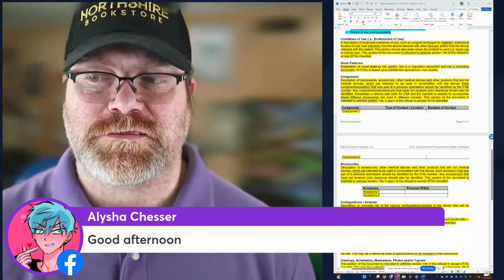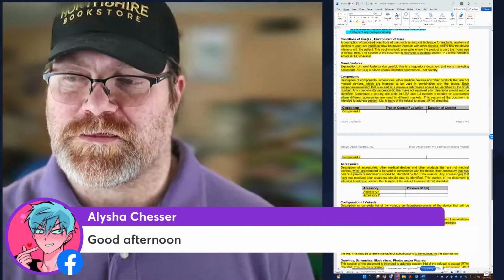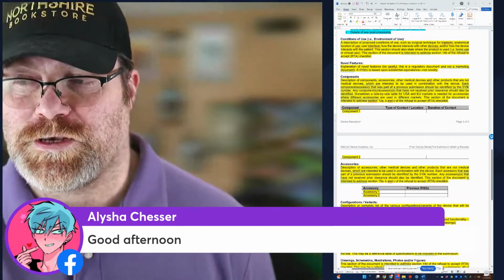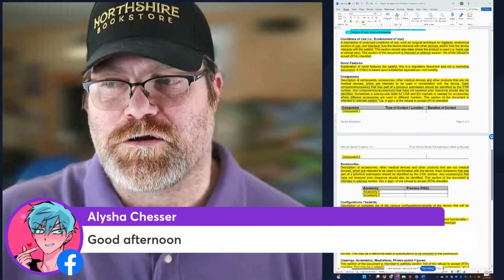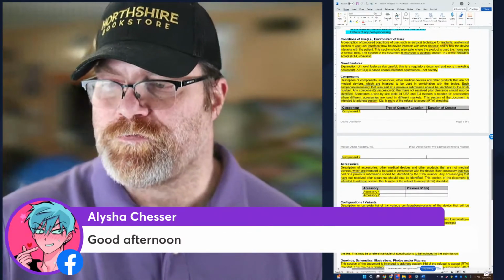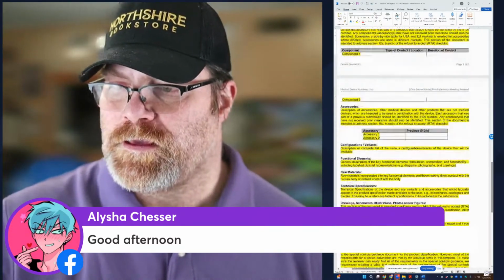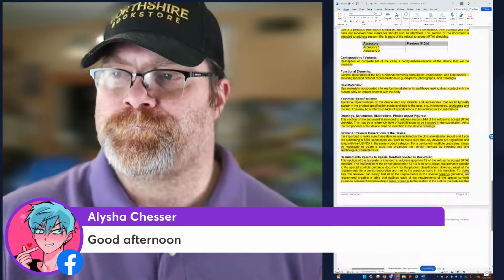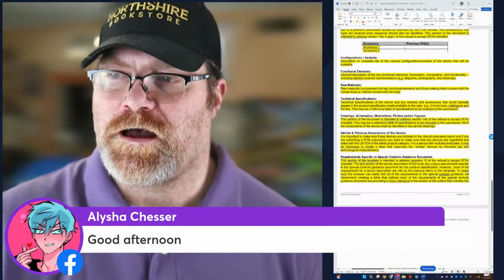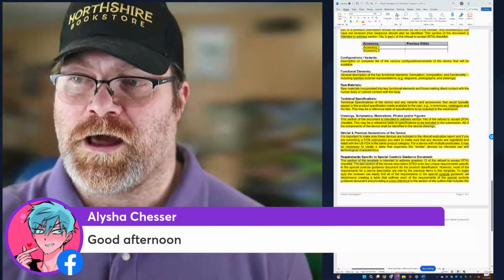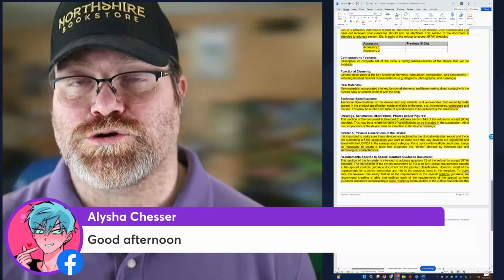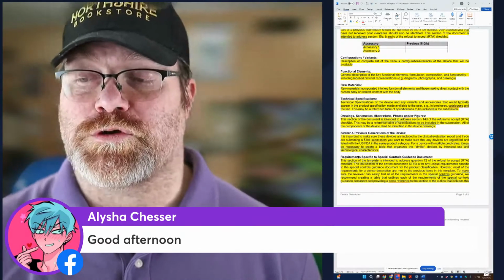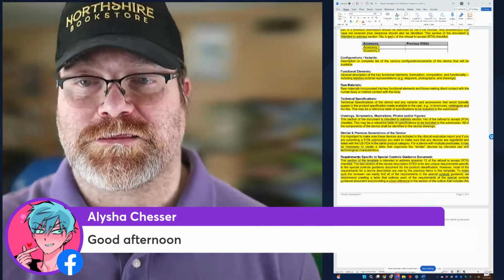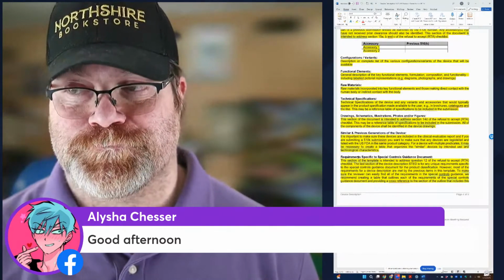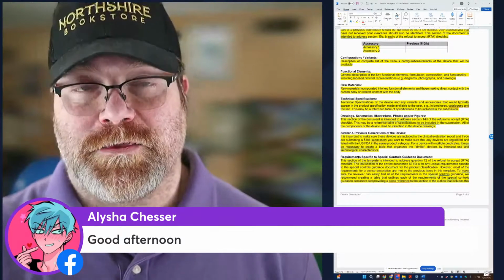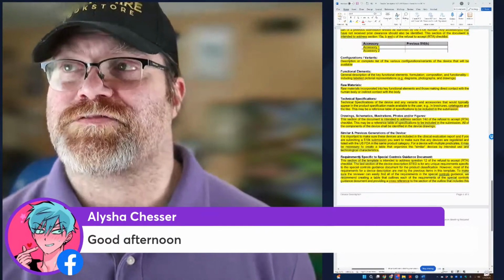Configurations and variants that we talked about before, that's a duplicate, so that might be something that you don't need because you've already got it in the eSTAR as well. Another thing that we found, if we scroll down here a little bit, in the past, a lot of people would not realize that there's a special controls guidance document. The special controls guidance document includes a list of what should be in your device description. But in our new eSTAR, they have sections for that.